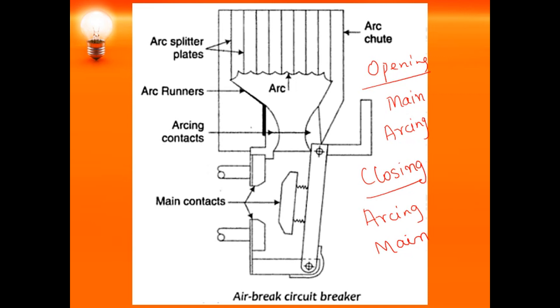When the fault occurs, the main contacts get separated and an arc is formed. Due to electromagnetic forces and thermal action, the arc moves upwards. The arc is formed across the arcing contacts and slowly moves upward along the arc runners. Finally, it reaches the arc splitter plates where it gets split. When it reaches the plates and gets split, the resistance increases and the arc is quenched. This is how the air break circuit breaker works.